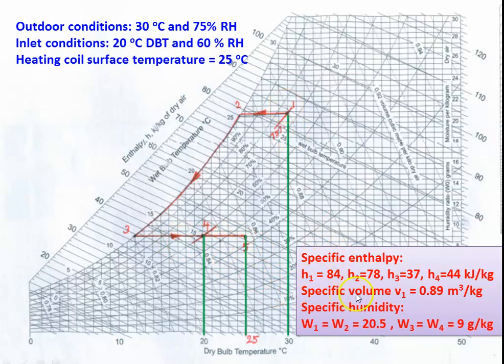From the chart: h1 = 84, h2 = 78, h3 = 37, and h4 = 44 kilojoules per kilogram. Specific volume of air at inlet condition is 0.89 cubic meter per kg. Specific humidity: w1 = w2 = 20.5 g/kg, and w3 = w4 = 9 grams per kilogram.